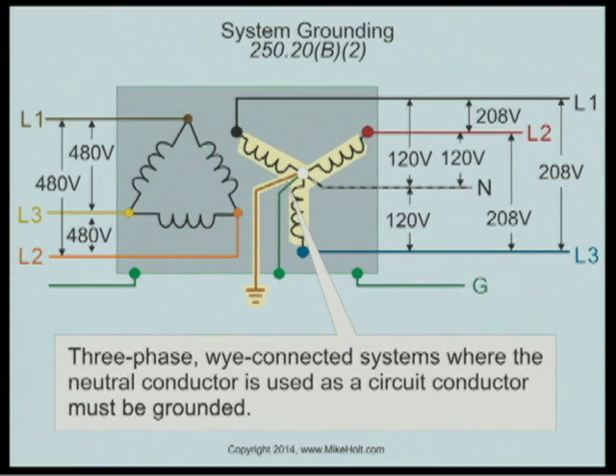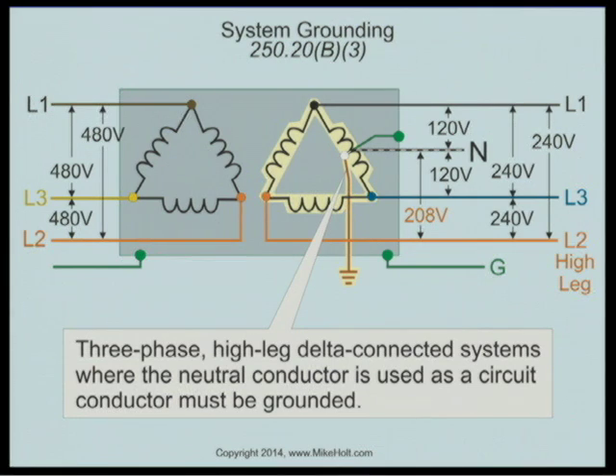Let's go back to our graphic. Since this is a Y secondary and it's a 120/208, you have line-to-neutral loads. It has to be grounded. Here is a delta high-leg system, and because we have line-to-neutral loads, the system has to be grounded. So if you want line-to-neutral loads, you have no choice. You're going with a grounded system. There is no option.